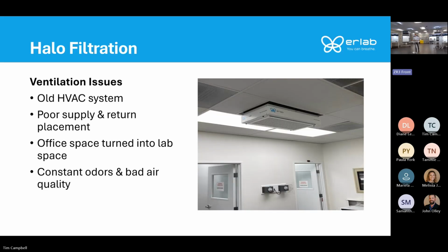Now the halo isn't just for lab spaces. That's where it started. That's where we saw most of them. But throughout your building, you may have air quality issues. You may have air quality issues in the kitchen, in the offices outside the lab. Maybe there's re-entrainment happening in your lab space, so some of the chemical vapors from one space are being transported to another. A halo is a cost-effective way to improve the air quality in all types of spaces in your facility. So it's going to help remove constant odors, bad air, as well as reduce overall particulates. If you're in an area with a lot of wildfire smoke, the halo can help reduce that as it's brought in through your HVAC system into your building. Because once it gets in your building, it's much harder to get that poor air quality out.